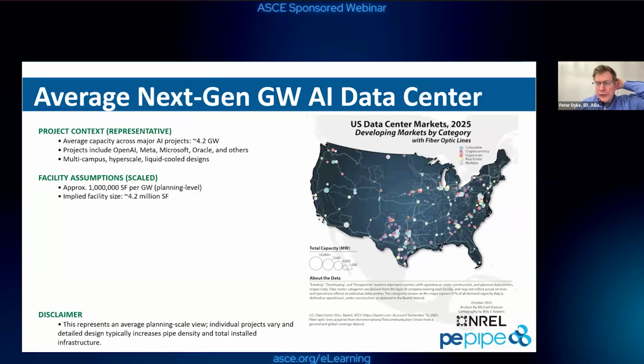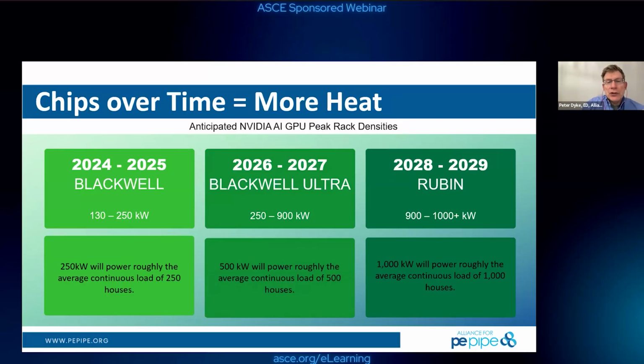If we go back to the previous slide: if we're able to handle the Blackwell today, which we are with the thicker walled PPRCT, what does a Rubin mean for us? Can we handle that heat? Yeah, 45 degrees C is still there, it's at the upper end of thicker walled PPRCT, it really just depends on the pressure ratings. I have a hard time believing, and I'm not an expert, that average temperatures get much higher than 45 C. I think other components within the server become the weak link that won't allow you to operate any hotter than that, but time will tell.